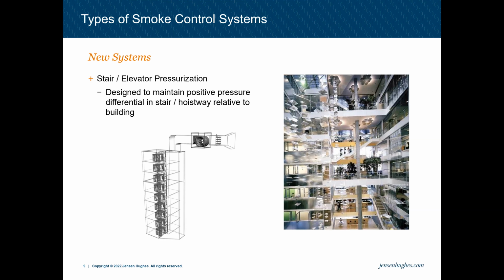It applies to stair shafts that extend 75 feet above our lowest level of fire department access. So in Massachusetts, we can technically have a high-rise building without requiring stair pressurization based on that 5-foot difference. And then we also have stair pressurization in underground buildings, for a shaft extending 30 feet under, below grade, if you will.